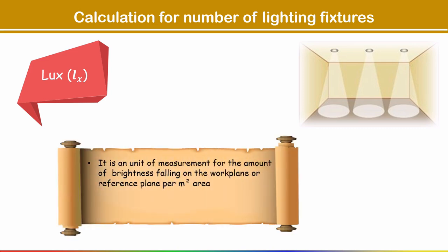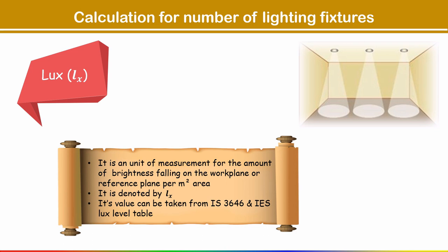The next term is LUX. It is a unit of measurement for the amount of brightness falling on the work plane or reference plane per meter square area. It is denoted by LX. Its value can be taken from IS 3646 and the IES LUX level table, based on your location — whether you are designing for an office space, bedroom, corridor, or dining hall.